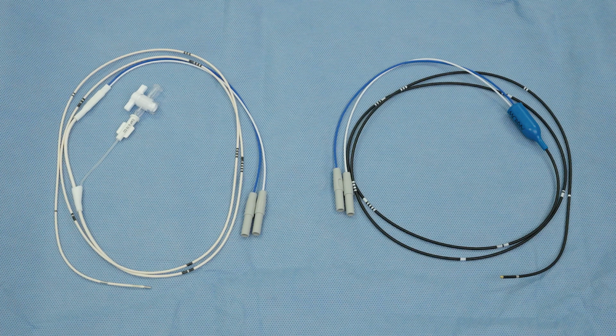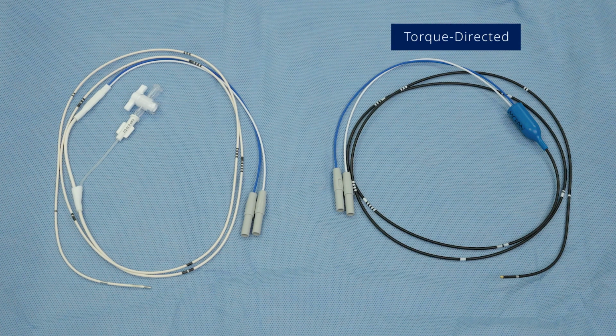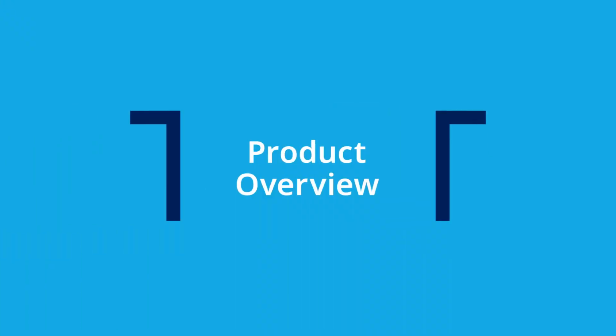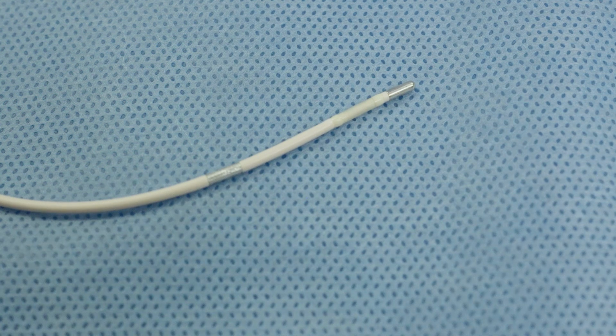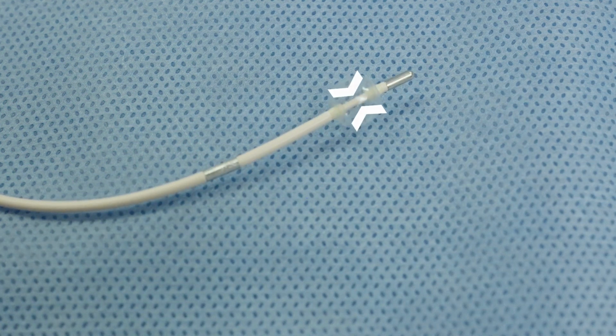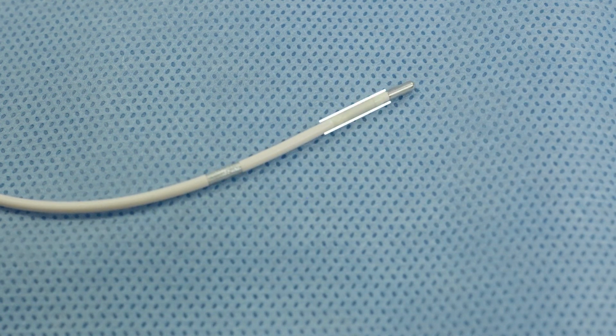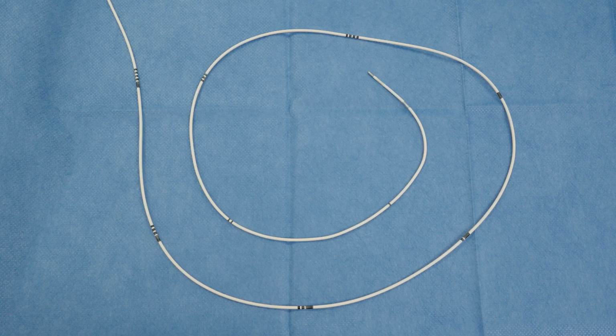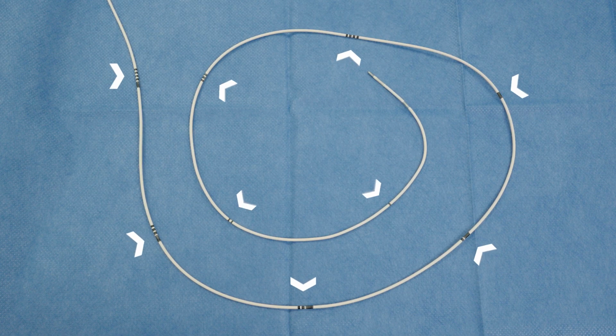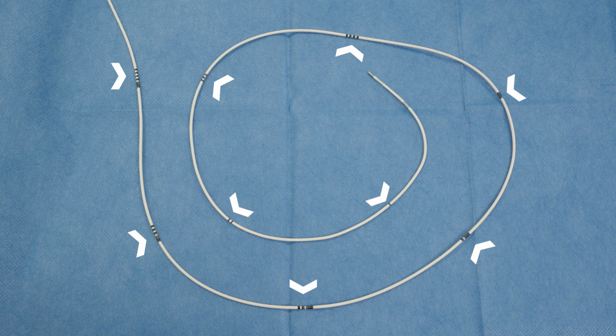There are 2 options available for catheter configuration. One is a torque-directed catheter, and the other is a flotation catheter with a balloon at the distal end of the catheter to allow flotation of the catheter through the right atrium and into the right ventricle. The catheter is tapered underneath the sleeve to ensure that the deflated sleeve does not exceed the external diameter of the catheter. The temporary pacing catheter is a radiopaque polymeric catheter with length markings printed every 10 centimeters.